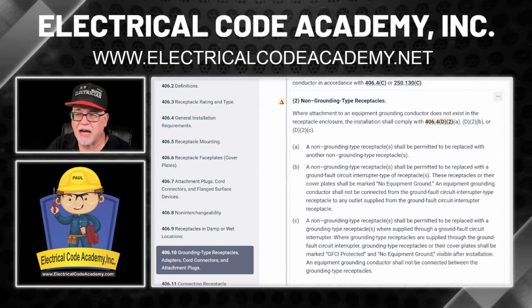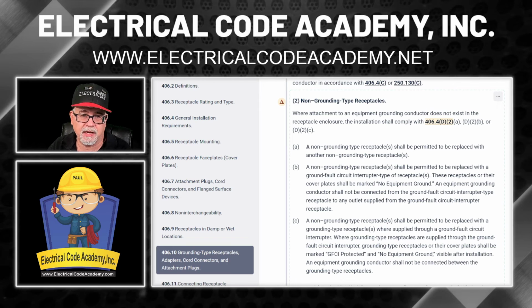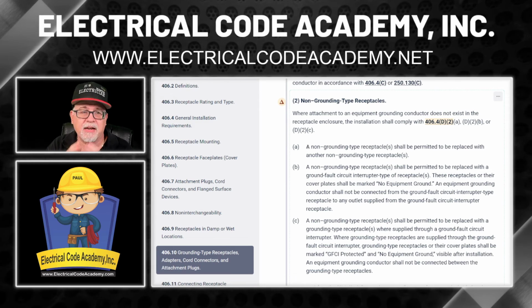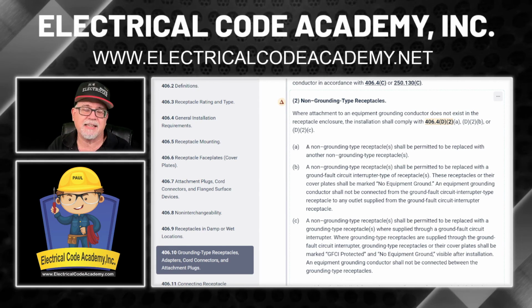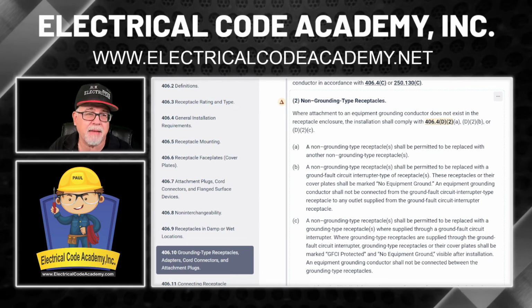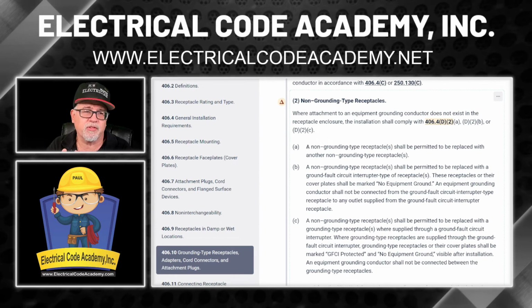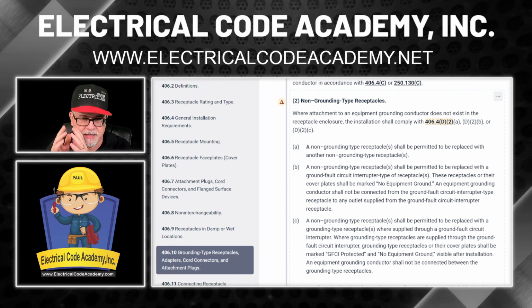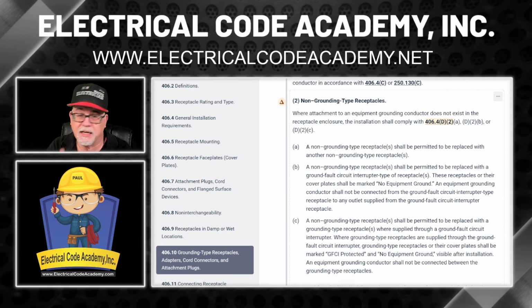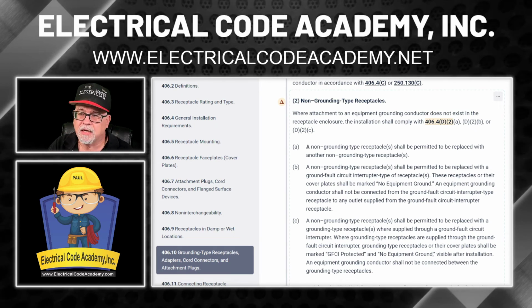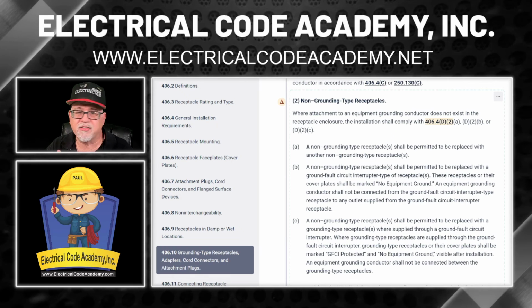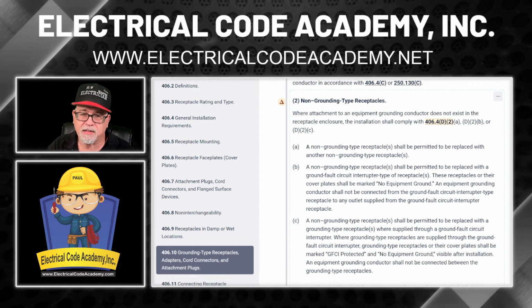No, you're not going to be using the equipment ground into it. Okay. You want to make sure that you don't connect anything at this point to anything that might be going downstream of this receptacle, this GFCI receptacle, if you're using it in this fashion. Okay. And it tells you that point blank. Obviously, the GFCI is not establishing an effective ground fault current path.